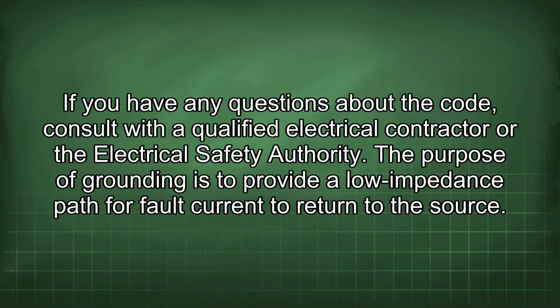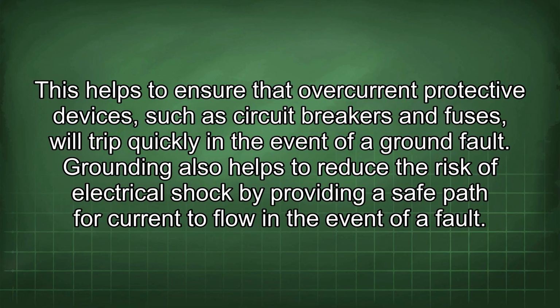The purpose of grounding is to provide a low impedance path for fault current to return to the source. This helps to ensure that overcurrent protective devices, such as circuit breakers and fuses, will trip quickly in the event of a ground fault. Grounding also helps to reduce the risk of electrical shock by providing a safe path for current to flow in the event of a fault.